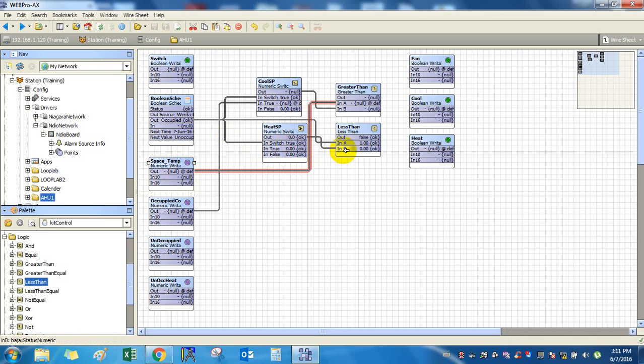Add an OR gate from your logic folder. Drag and drop it to your wire sheet. Whenever your cooling or heating is on, you have to switch on your fan. Also your fan will be running throughout your occupancy mode, so I will add another OR block. Whenever the system is in occupied mode or whenever there is a heating or cooling requirement, at that time you have to enable your fan. So link the out of this block to your fan command.